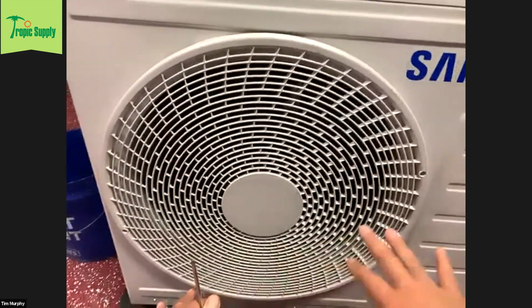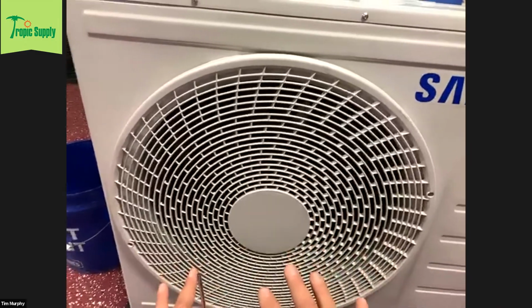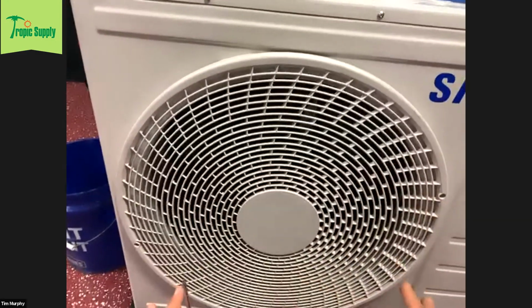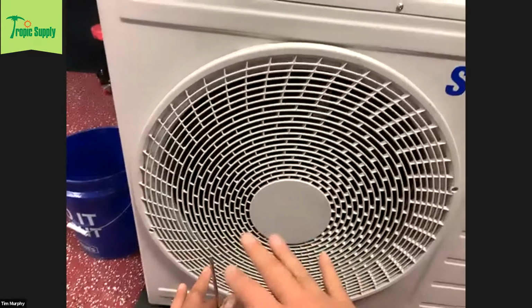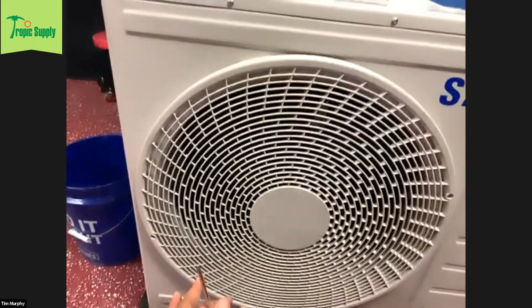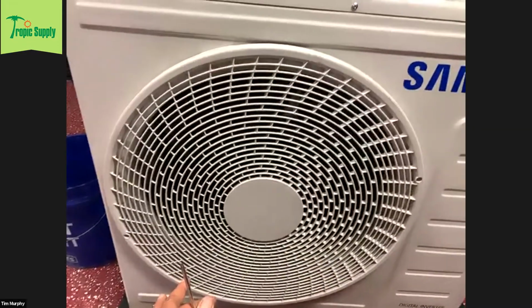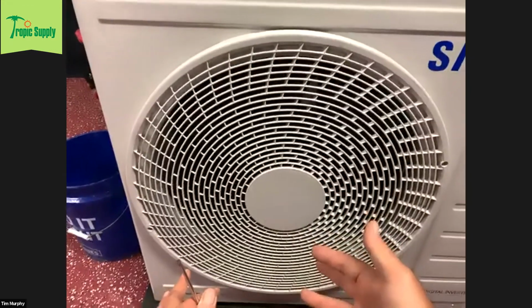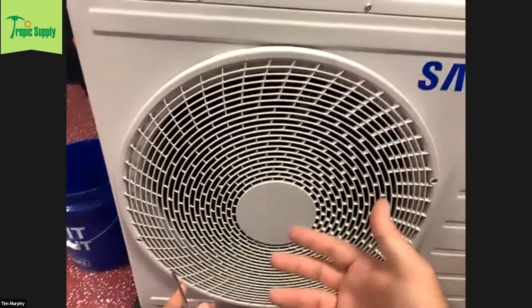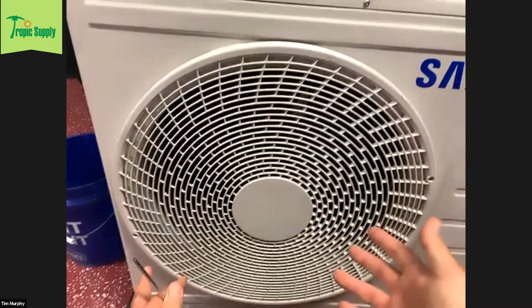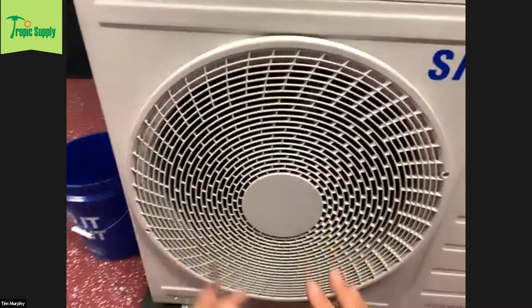But in those instances where it is on the ground, you're going to notice, just like any condenser, a lot of buildup in the bottom of this. Anytime we do maintenance, we want to clear all that out. We don't want dirt and grime sitting along the bottom of the coil, because that's going to speed up whatever corrosion process there is. It is coated, but that doesn't mean we want to throw salt and dirt on it. We still want to keep it clean and maintain it.